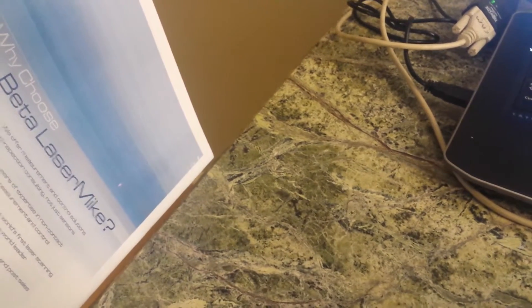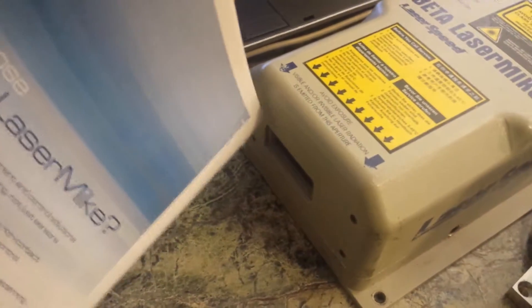Now you will see that one thing is you want there's a standoff distance. You can see the two laser beams right there. As I move the paper farther back it gets to the depth of field of about 11.8 inches which is 300 millimeters from the face of the gauge.